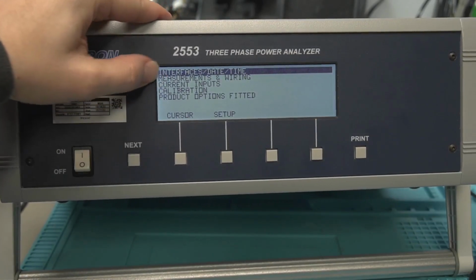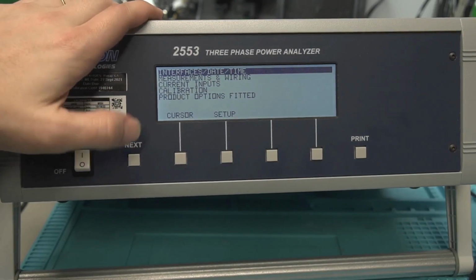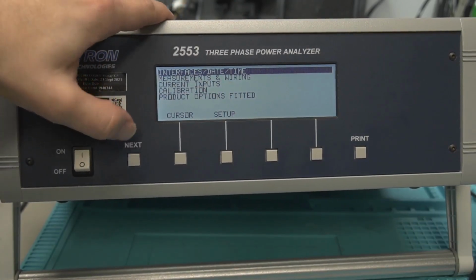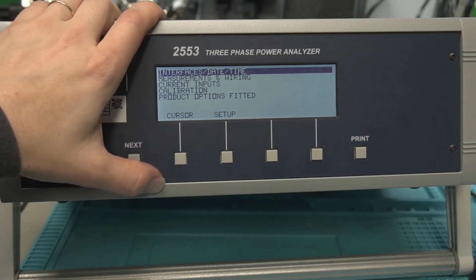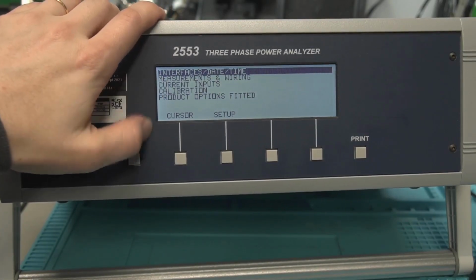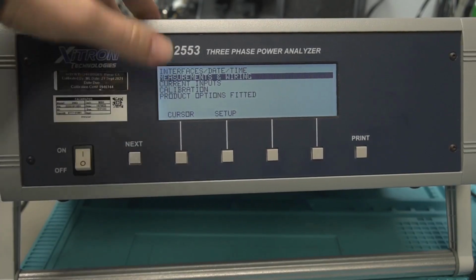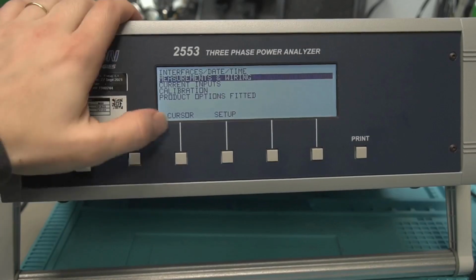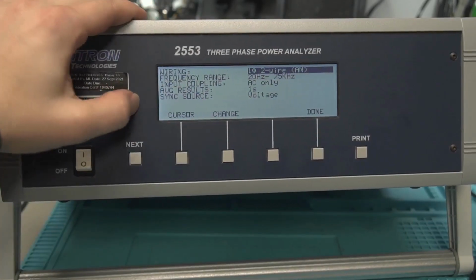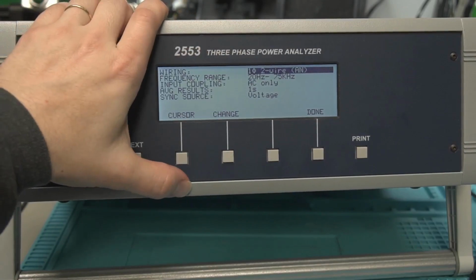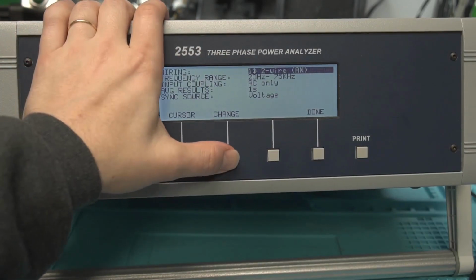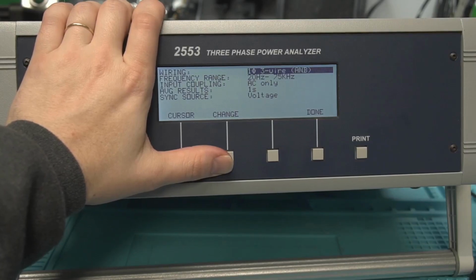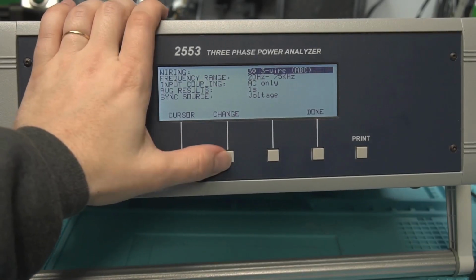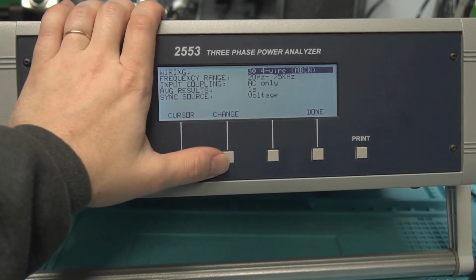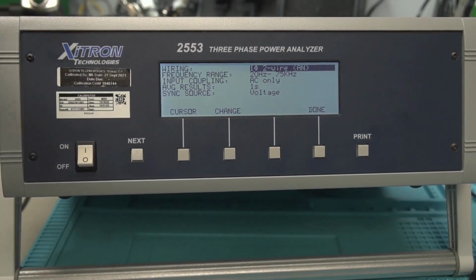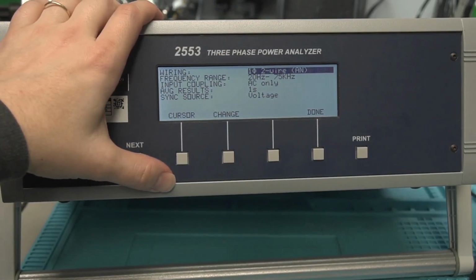Your first one is your interface. The way the menu works here is this next kind of cycles you through these main screens here. And then once you get to this last screen, which is the setting screen, you use the cursor and it just moves it down. It just is a down on the cursor. And so we go to setup here and we can change our wiring. So to do that, instead of hitting cursor, you're going to hit change. You can go 1-phase 3-wire, 1-phase 2-wire, 3-phase 3-wire, and 3-phase 4-wire. So that would be what I have here in my office. So that's what we'll be using.